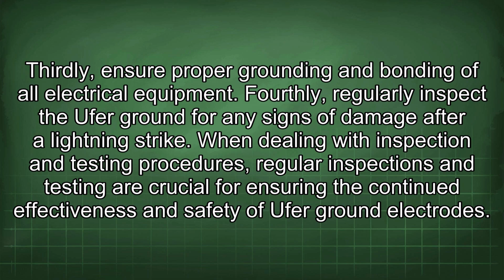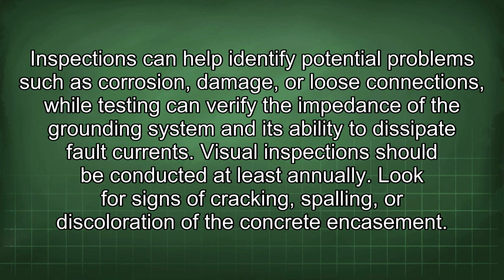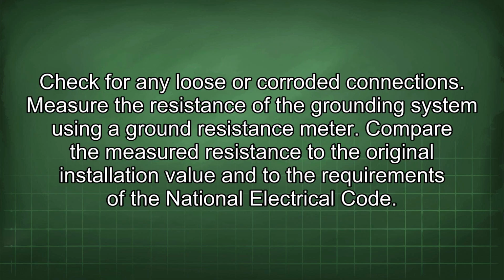When dealing with inspection and testing procedures, regular inspections and testing are crucial for ensuring the continued effectiveness and safety of Ufer ground electrodes. Inspections can help identify potential problems such as corrosion, damage, or loose connections, while testing can verify the impedance of the grounding system and its ability to dissipate fault current. Visual inspections should be conducted at least annually. Look for signs of cracking, spalling, or discoloration of the concrete encasement. Check for any loose or corroded connections.